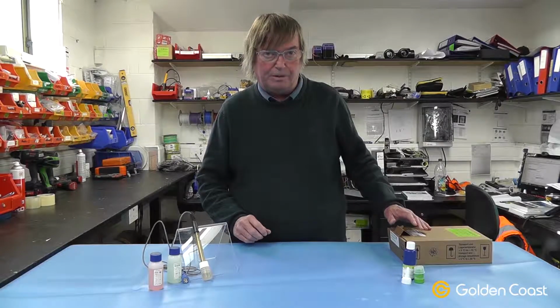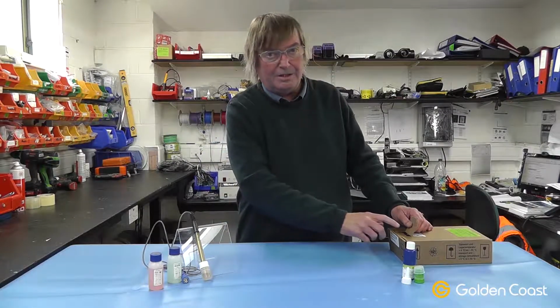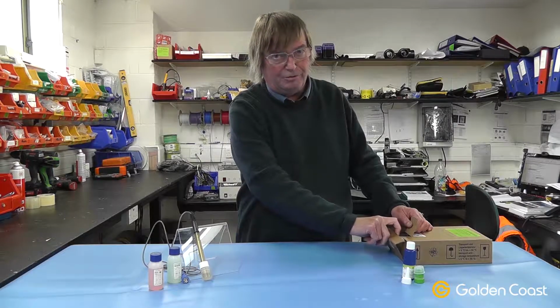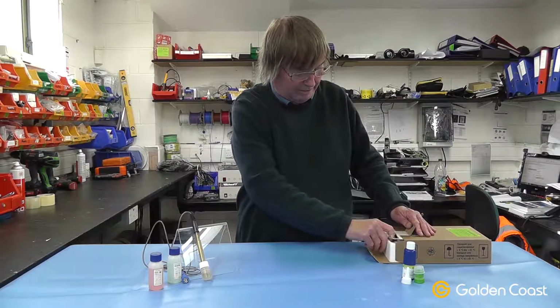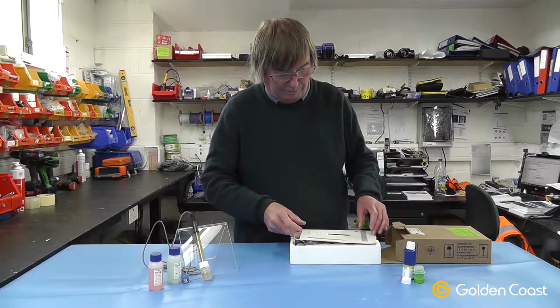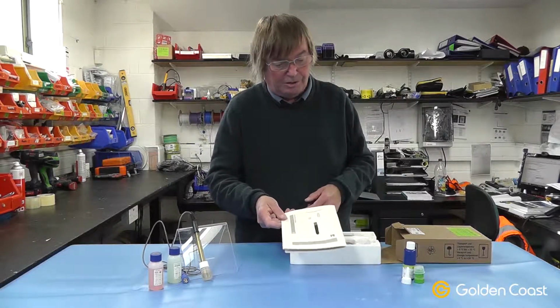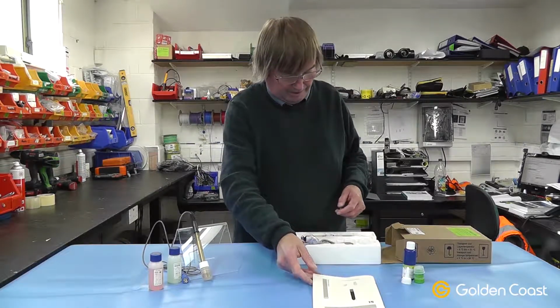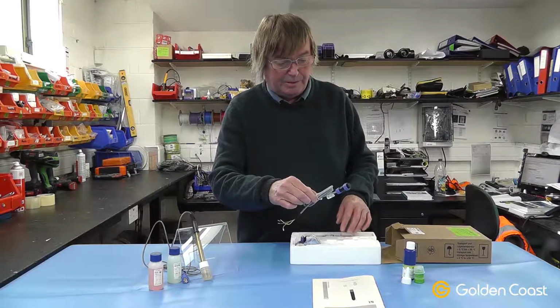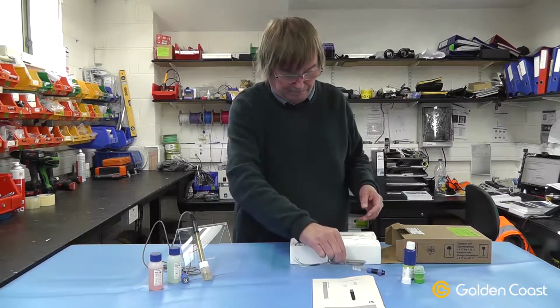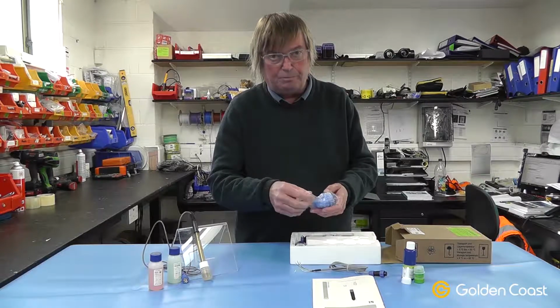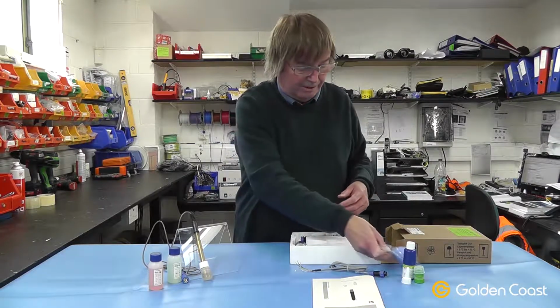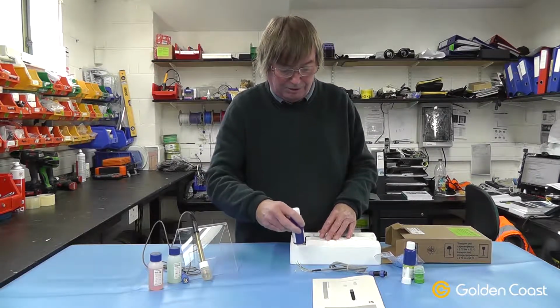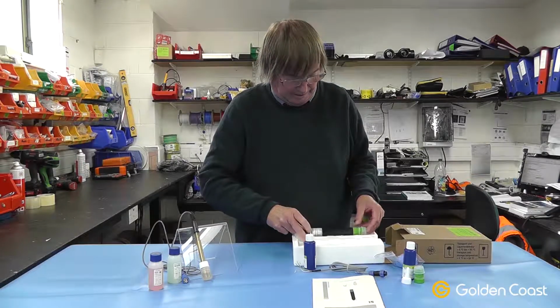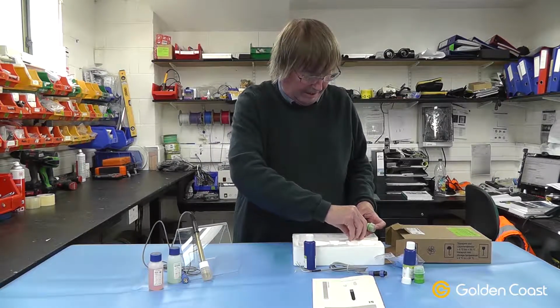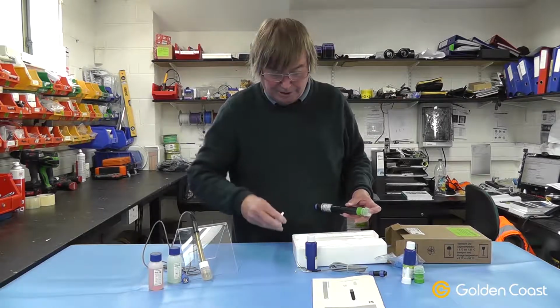The amperometric probe comes packed in a box and is a delicate electronic instrument, and it should be treated as such. So we'll just unpack it. It comes with full operating instructions which must be followed to the letter. You get a cable, if you need a spare cable, with an M12 connector, a set of rubber gloves that should be worn when you're putting in the electrolyte gel, the electrolyte gel itself, the probe, and the filler cap that goes with the gel.